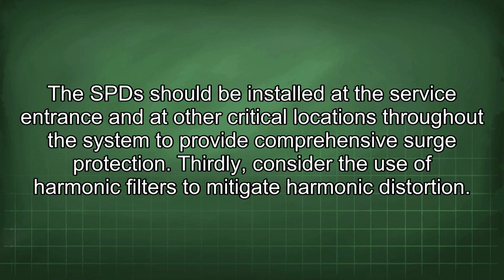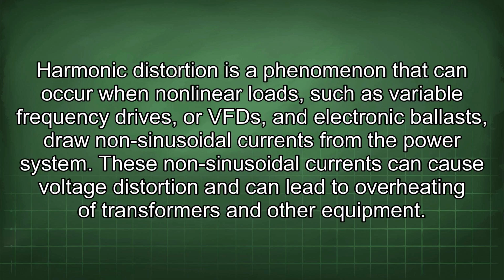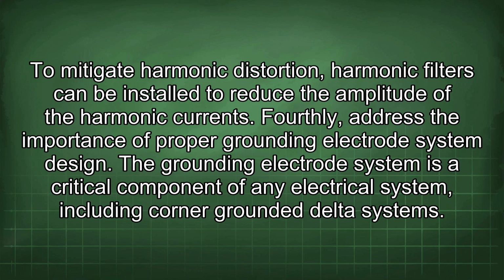Thirdly, consider the use of harmonic filters to mitigate harmonic distortion. Harmonic distortion is a phenomenon that can occur when nonlinear loads, such as variable frequency drives, or VFDs, and electronic ballasts, draw non-sinusoidal currents from the power system. These non-sinusoidal currents can cause voltage distortion and can lead to overheating of transformers and other equipment. To mitigate harmonic distortion, harmonic filters can be installed to reduce the amplitude of the harmonic currents.